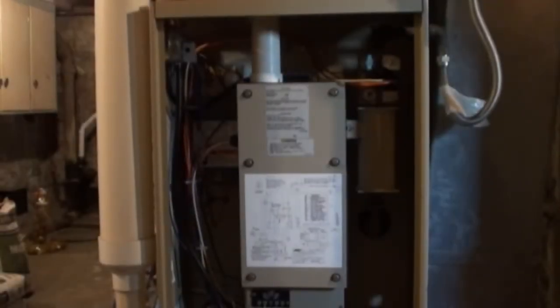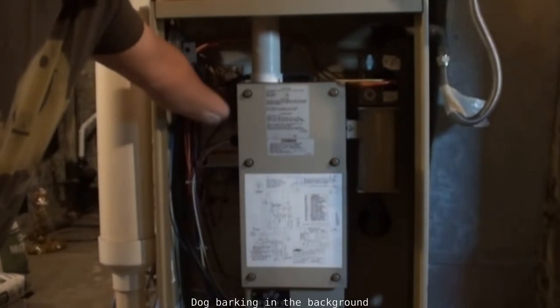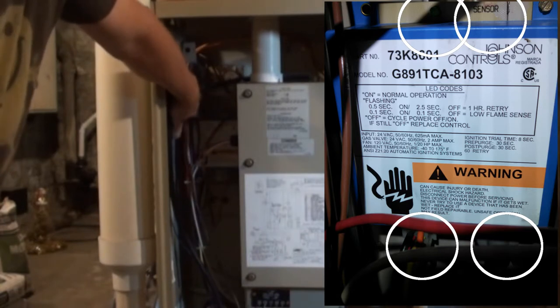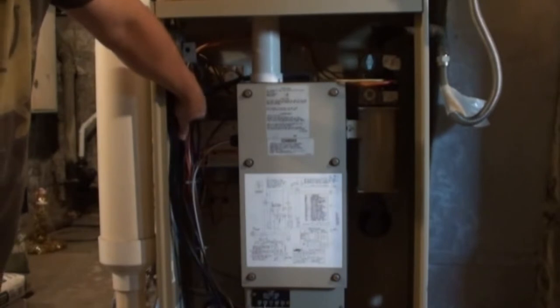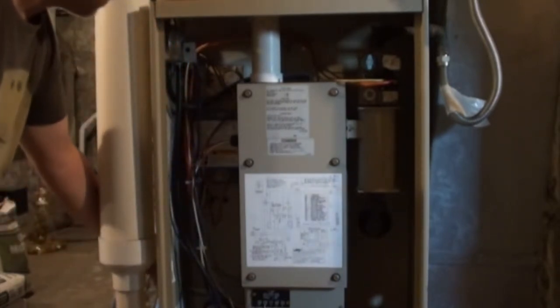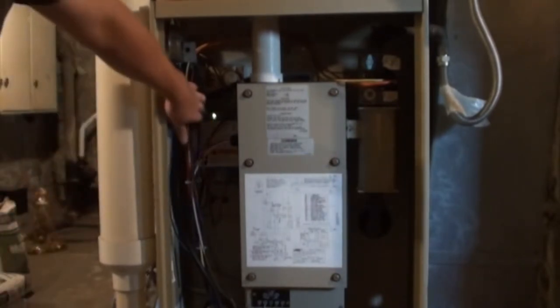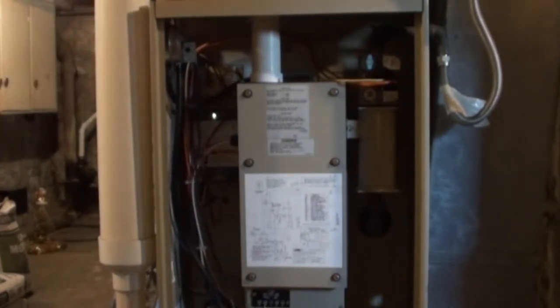All right, so we got the new controller board in there. Everything plugs up real simple. We got our main connector here, we got our spark wire here, and then we got our sense wire here. Our LED's up here on the top. So I'm going to flip the on switch, and then we should see that come on steady. And then we'll actually turn on the furnace and see if that works. Okay, so our green light is on steady, so that's a good sign. So let's turn on the furnace now, and then we'll see if it actually kicks in properly.